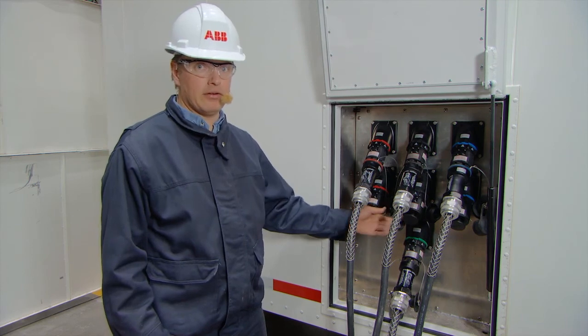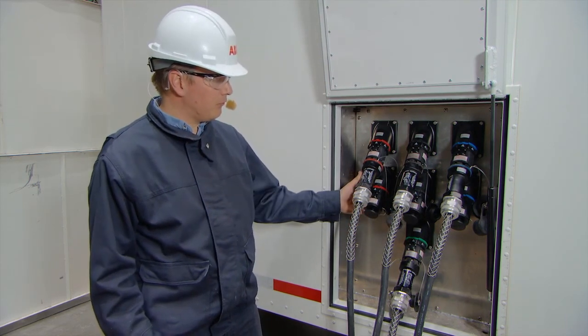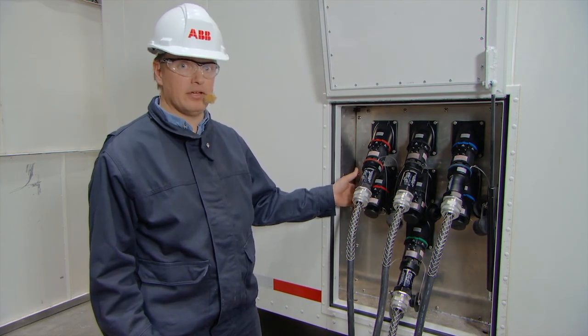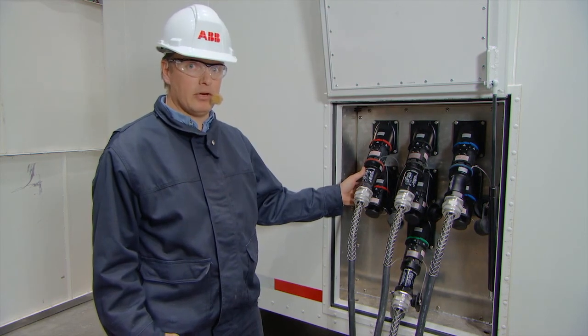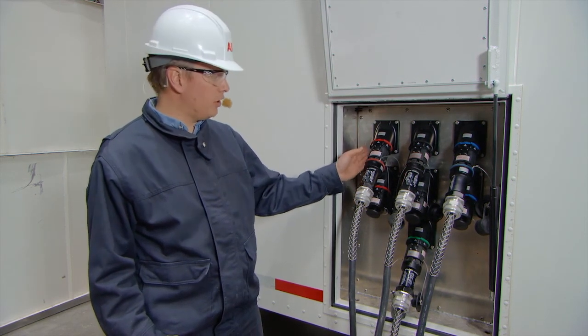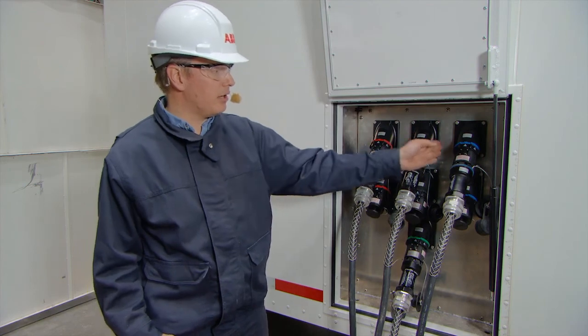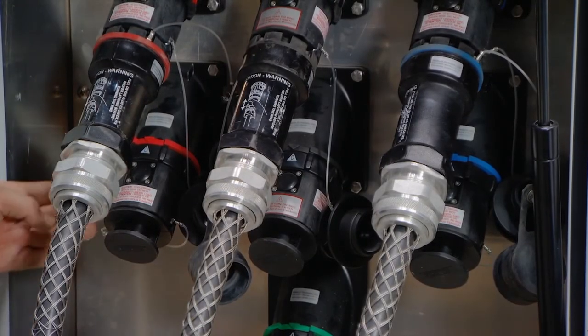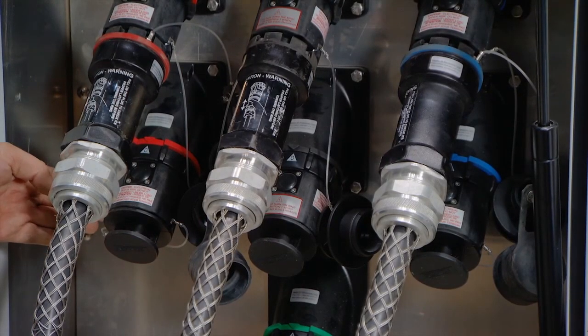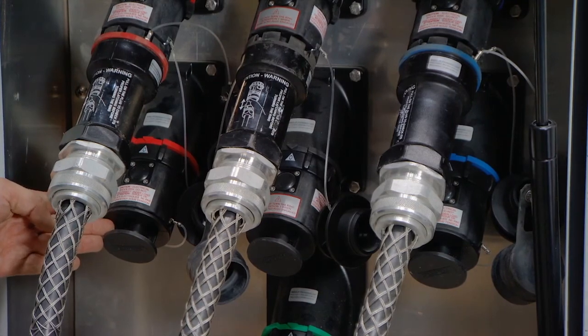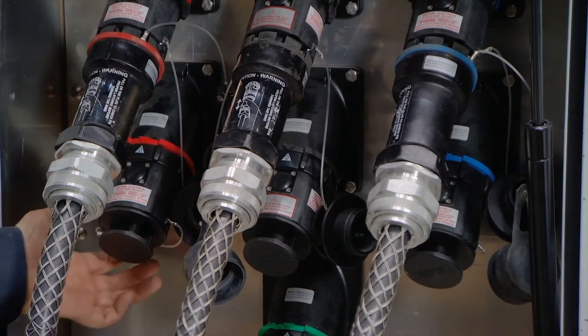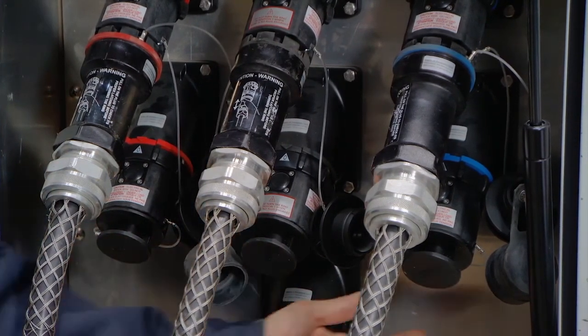Then you connect the second set in parallel with the first one and connect it to the same phase as the first one. The connections are keyed, so you should connect red to red, black to black, and blue to blue. And the ground to the ground. The 3 connections here which are now not connected are used for large transformers where more than 300 amperes is needed. That's for phase 1, 2 and 3.